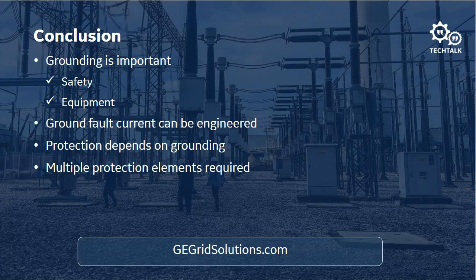And that is the 27TN, the third harmonic undervoltage element. As I mentioned, when a generator is normally running, there's third harmonic voltage being generated. And we can use that to set our 27. But it's difficult, as I mentioned, to set that 27TN element, because we need to know the levels of third harmonic. And it can change during the loading, power factor scenarios, the various load conditions, and system conditions of the generator. That third harmonic voltage will change.